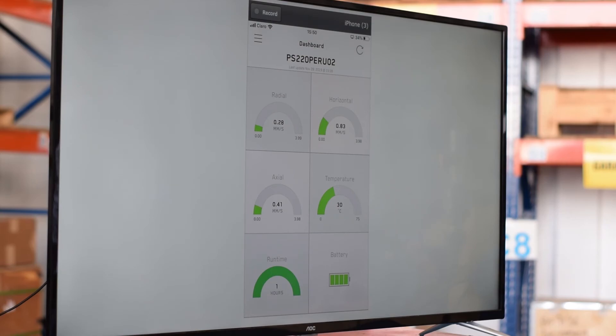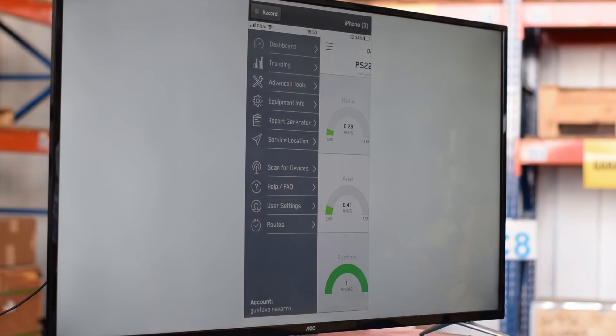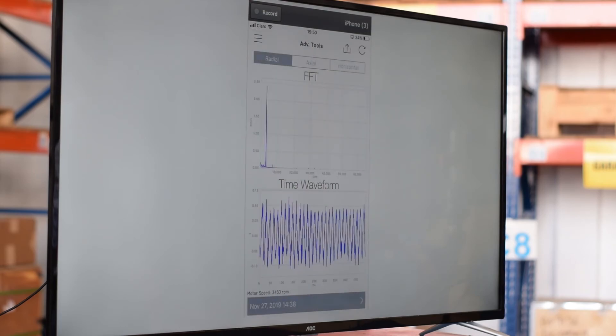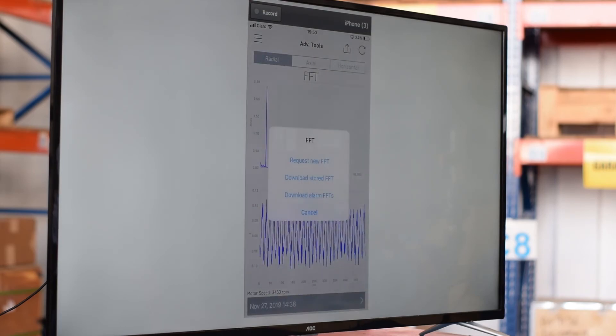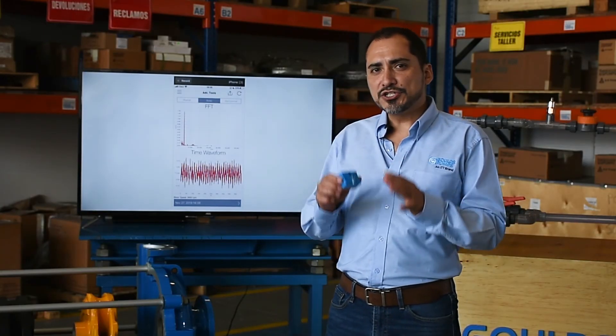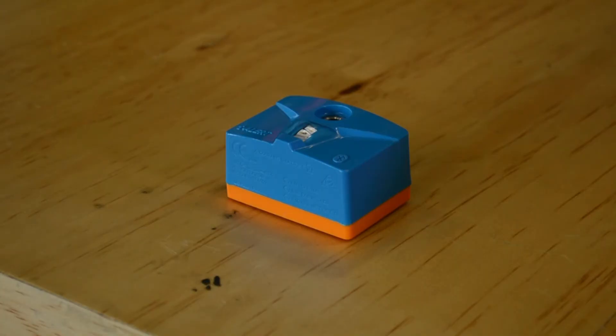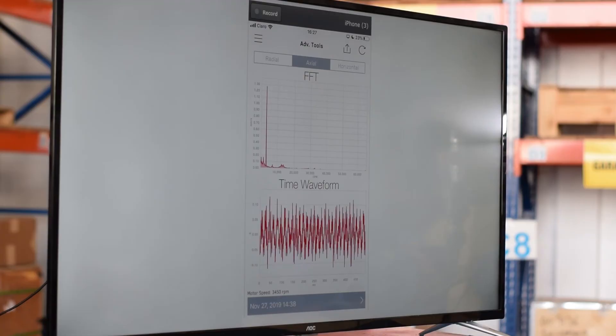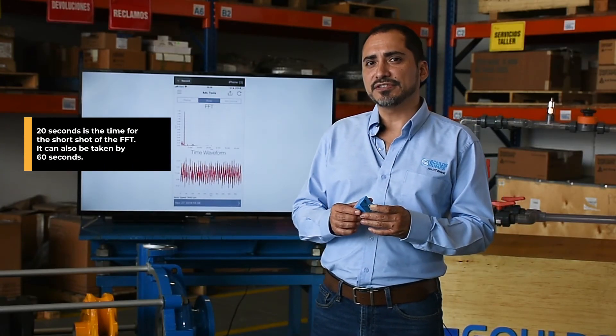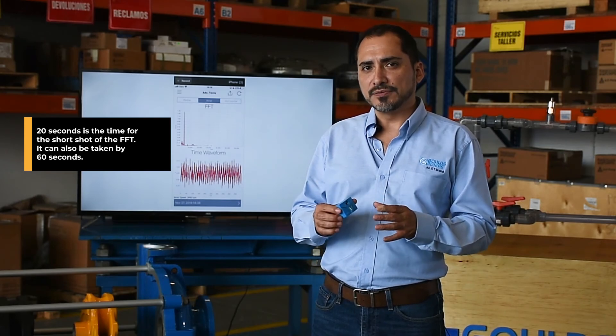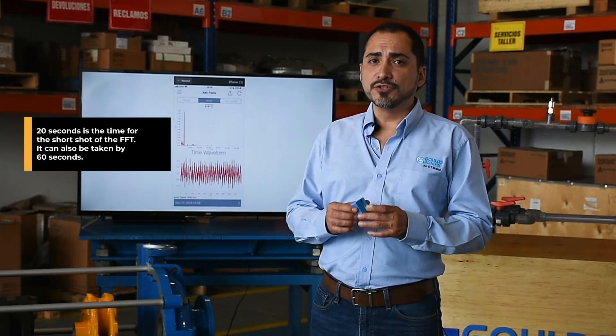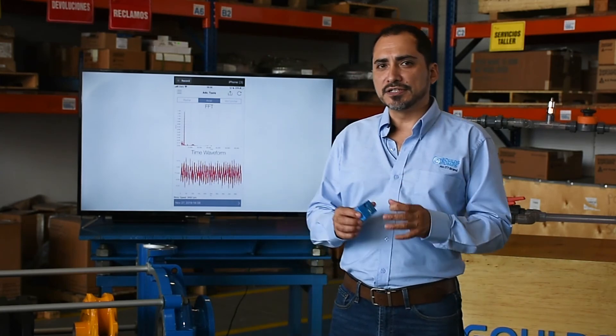With the iAlert app, we select the sensor. We touch the menu icon and advanced tools and we order the FFT. The app asks the sensor to measure the vibration for 20 seconds. Then the sensor itself performs the FFT algorithm. When finished, it sends the file with the time waveform and the FFT spectrum to the tablet. I want to emphasize that this is one of two ways to obtain the FFT. Probably the most useful is the automatic mode, when iAlert performs it every time it detects an alarm condition.